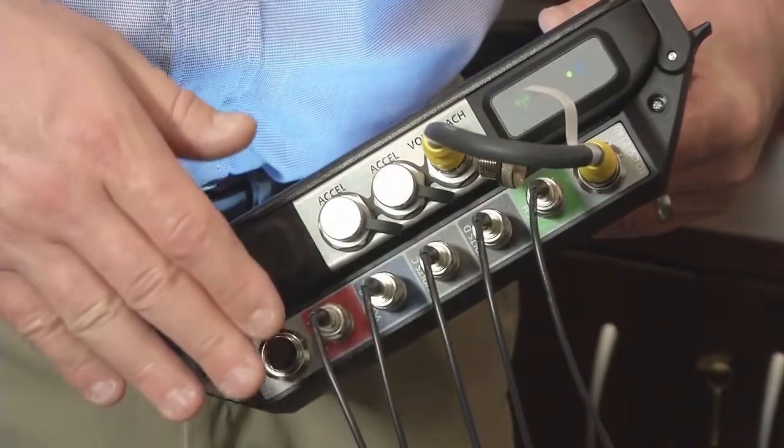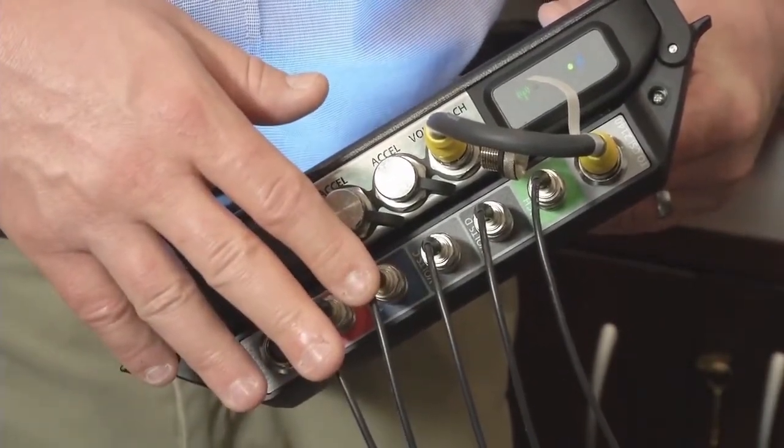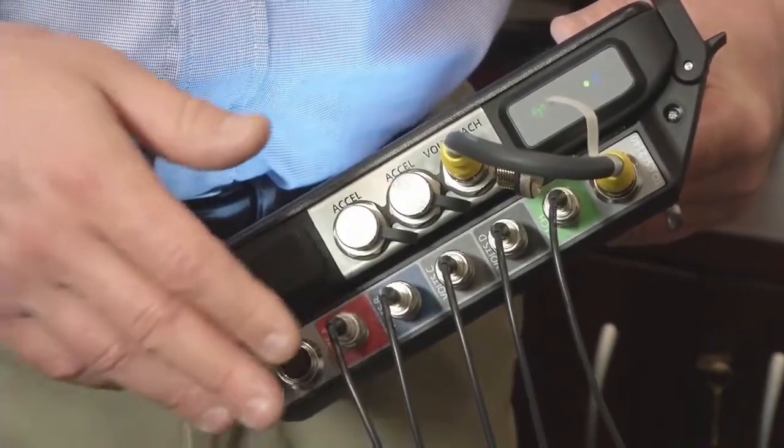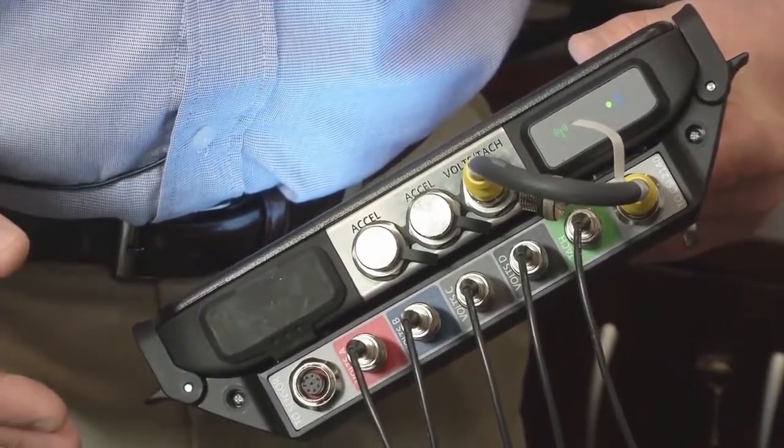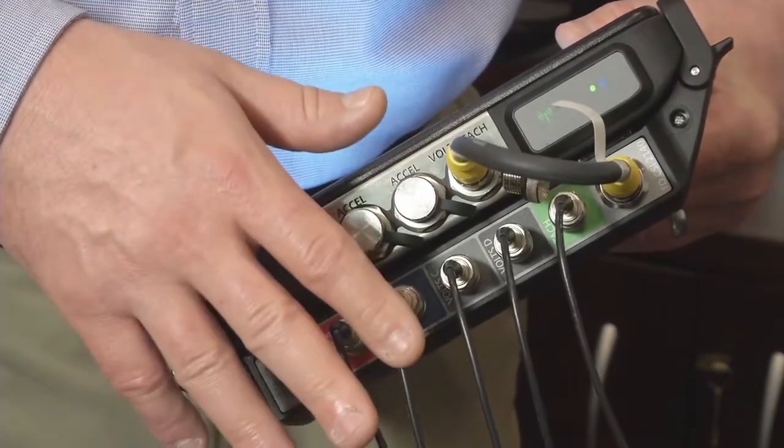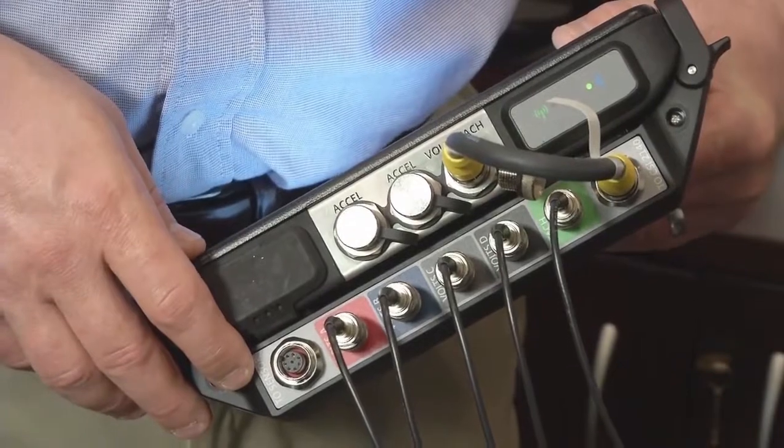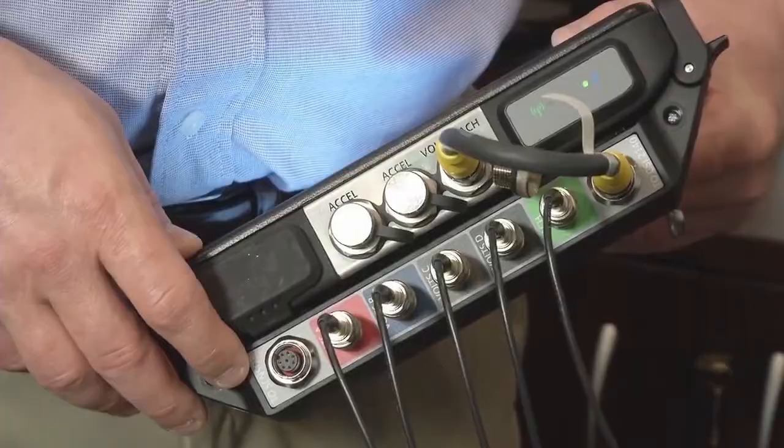Now the protection system, remember, is just there to shut down the machine in case something exceeds a vibration level. But it doesn't give you any diagnostic information about what went wrong or can you start the machine back up. And so that's why we're using the CSI 2140 to bring these signals in so we can understand the health of that sleeve bearing machine and can it be brought back up or is there something that needs to be corrected.